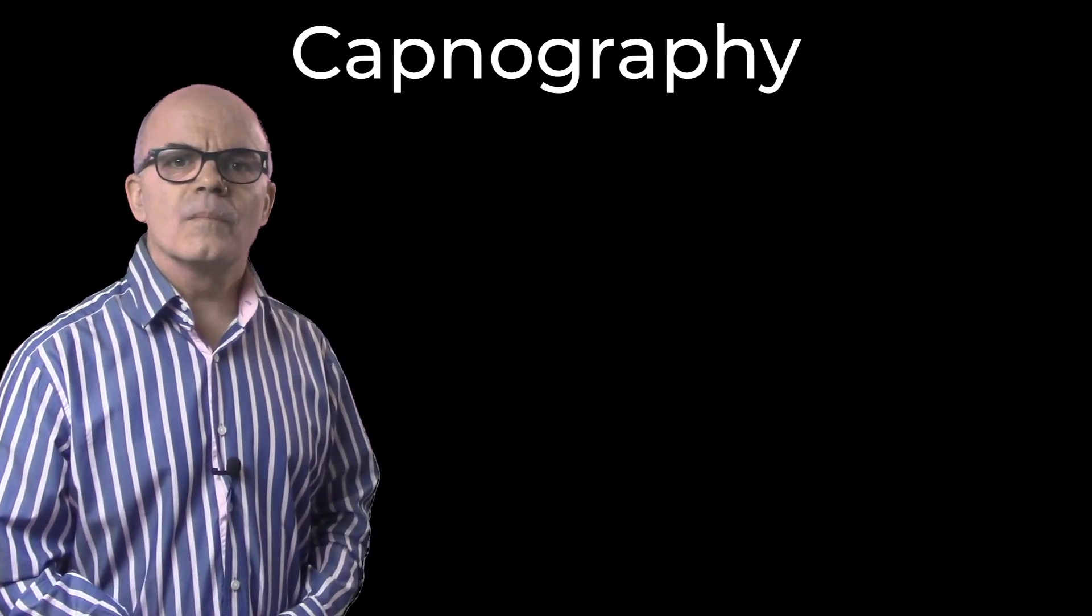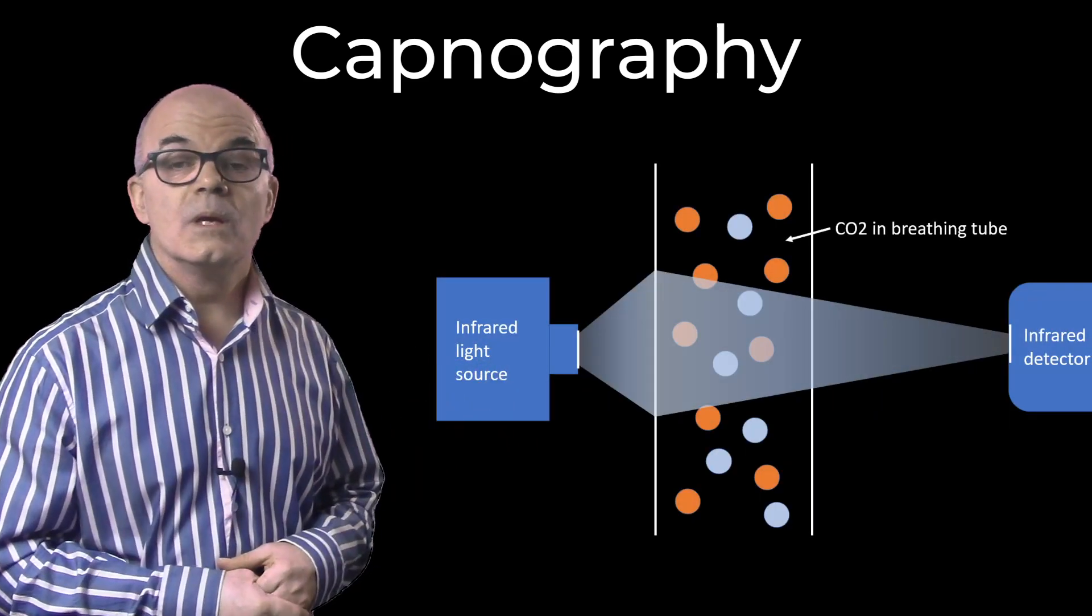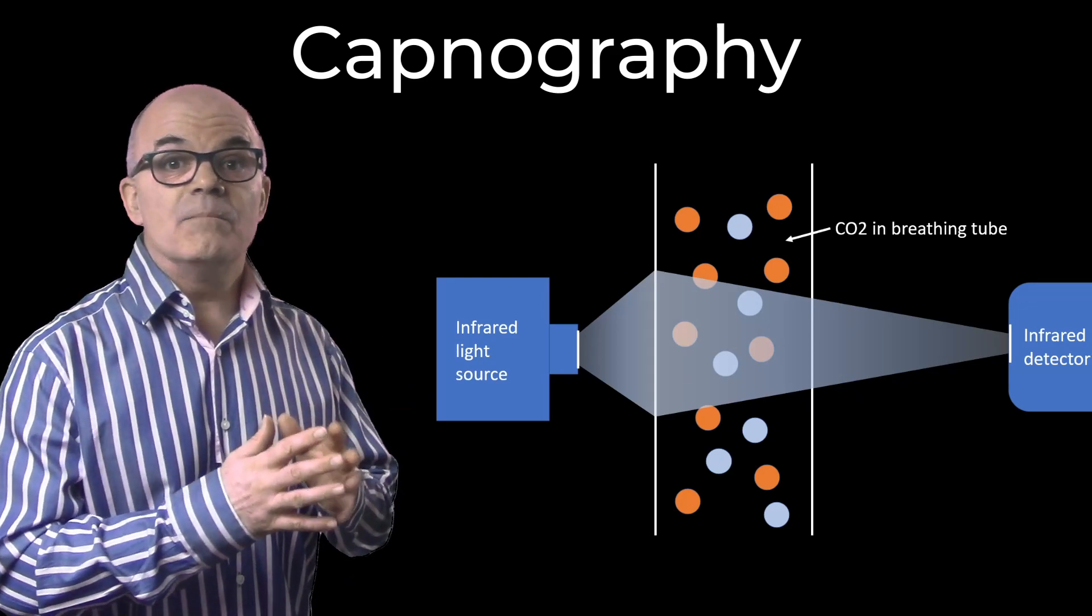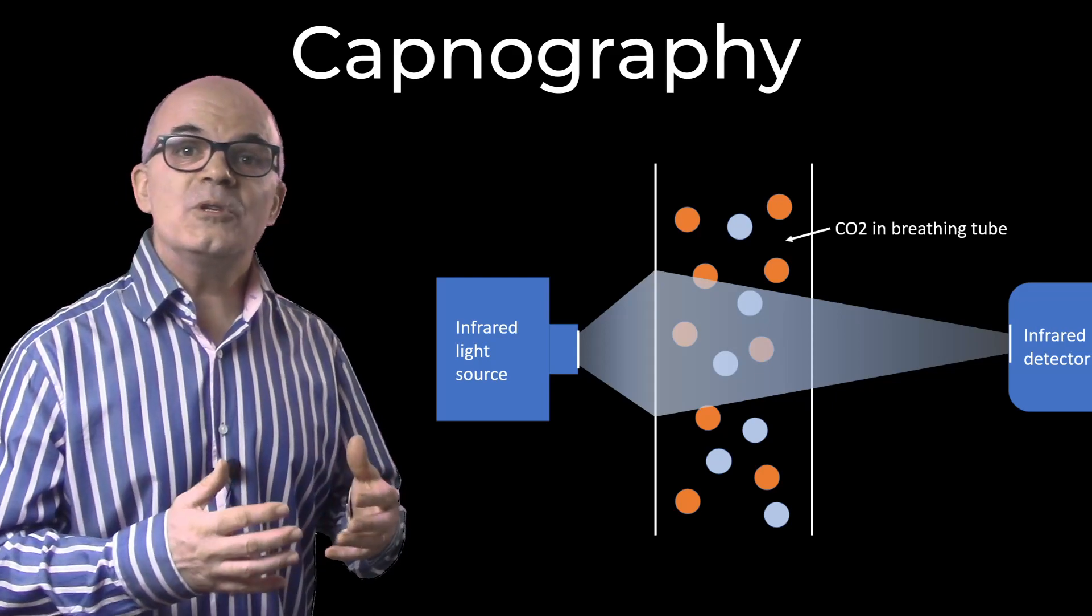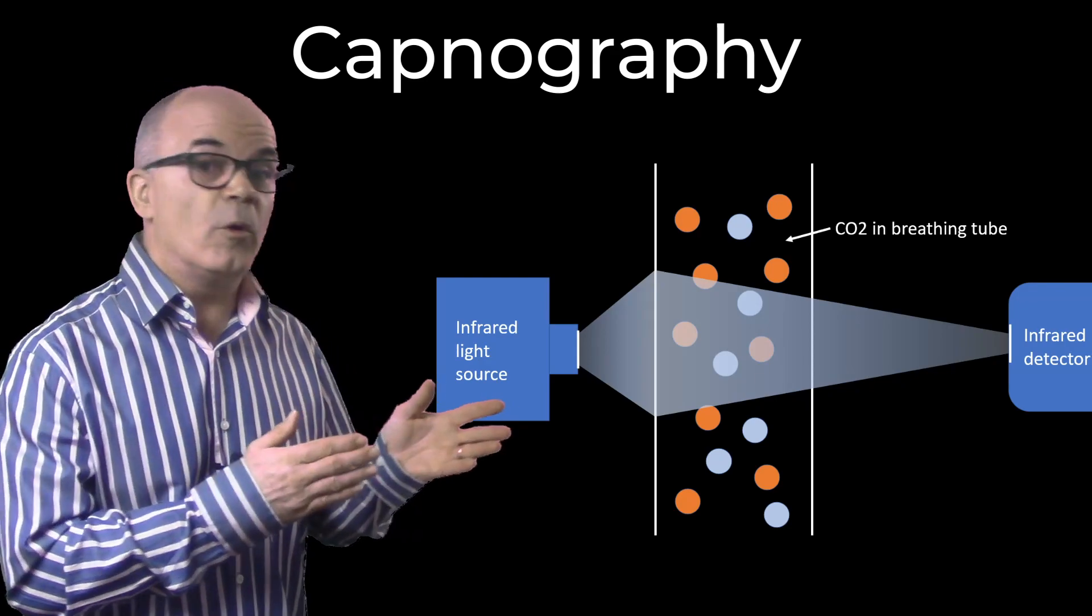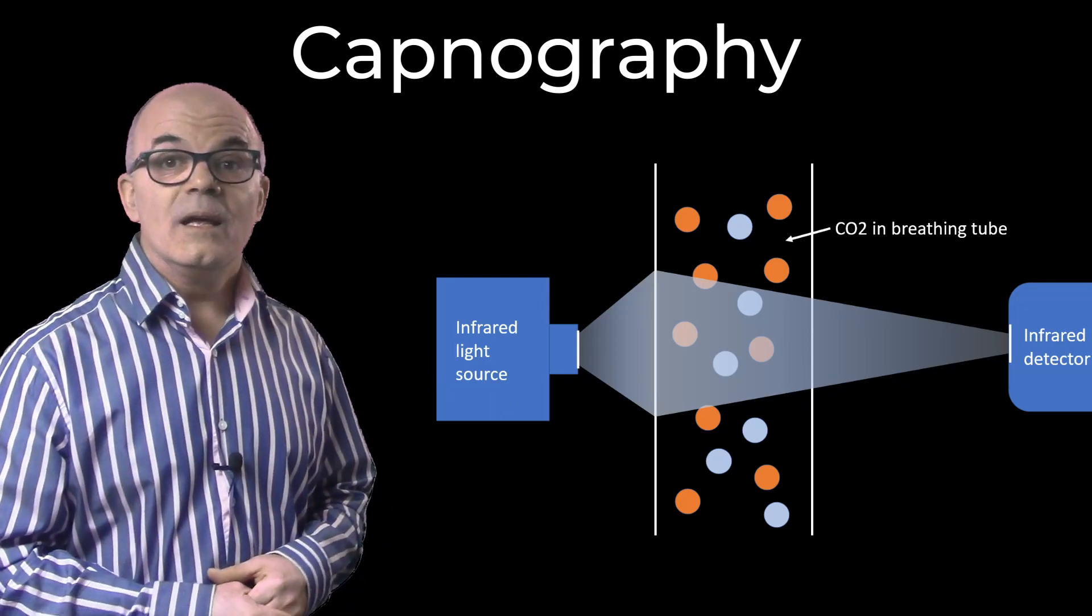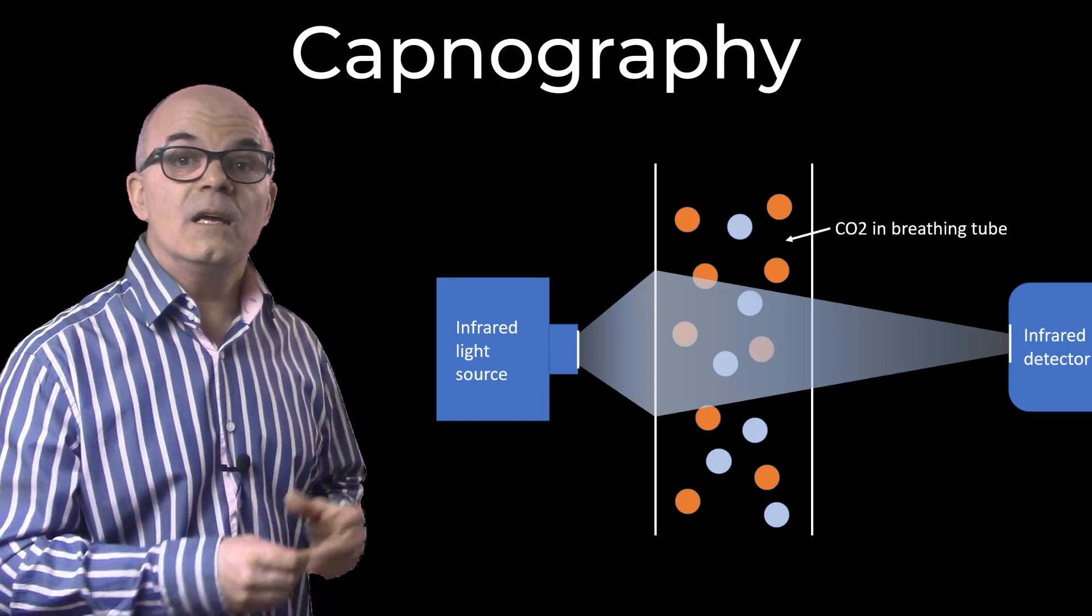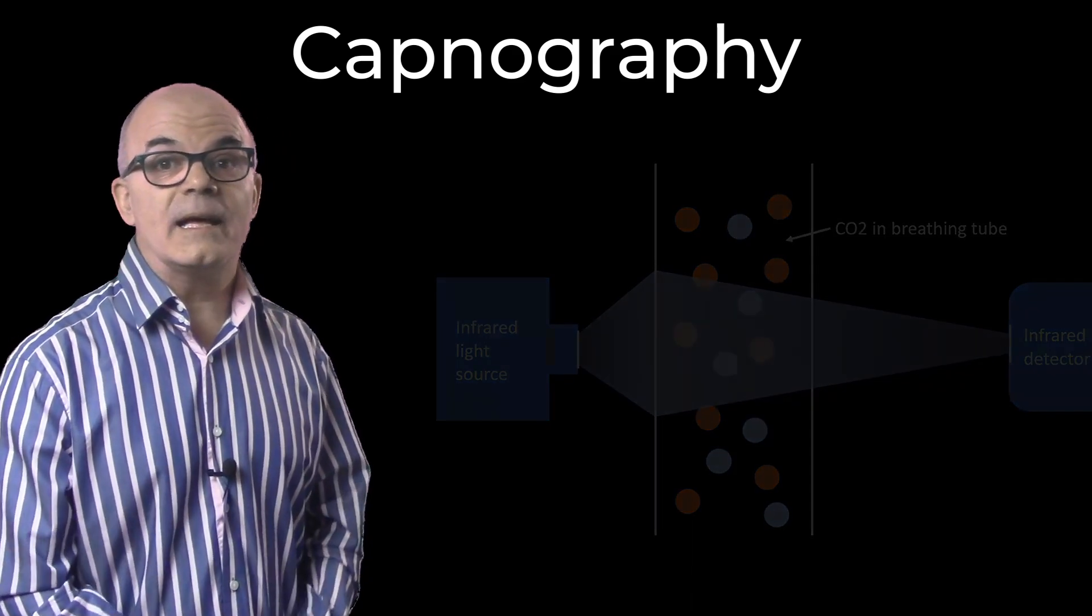How does it work? Infrared absorption spectroscopy. Two sides to the device: an infrared light emitter and an infrared light detector. As CO2 passes the emitter, light of a certain wavelength is absorbed by the CO2. The detector then senses this drop in the infrared light and translates this into a number or a graphical display.